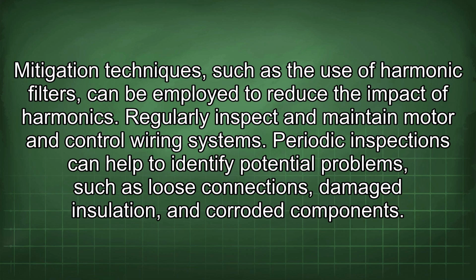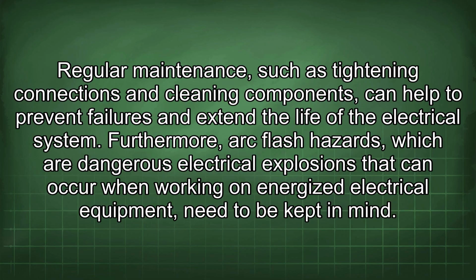Regularly inspect and maintain motor and control wiring systems. Periodic inspections can help to identify potential problems such as loose connections, damaged insulation, and corroded components. Regular maintenance, such as tightening connections and cleaning components, can help to prevent failures and extend the life of the electrical system. Furthermore, arc flash hazards, which are dangerous electrical explosions that can occur when working on energized electrical equipment, need to be kept in mind.